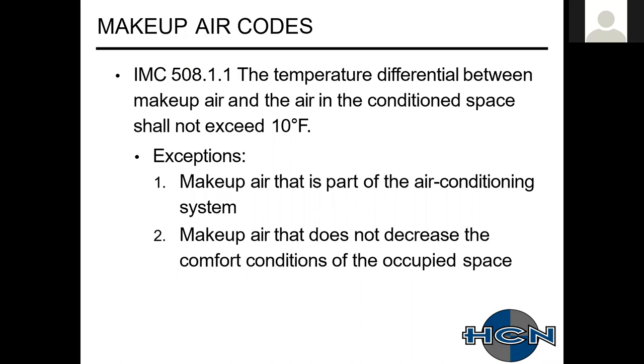So typically codes are what dictate most designs. For makeup air, IMC 508.1.1, 2015 is the year I pulled for this. It just requires that the temperature differential be 10 degrees. And then there's a couple of exceptions. And a lot of the time the exceptions are what a lot of manufacturers will pull out.